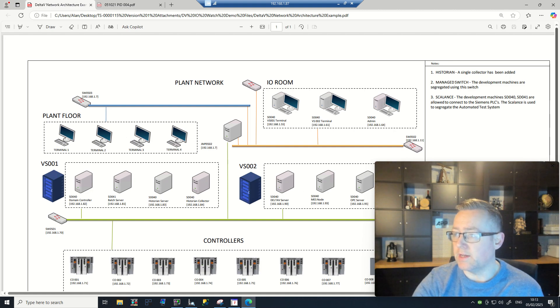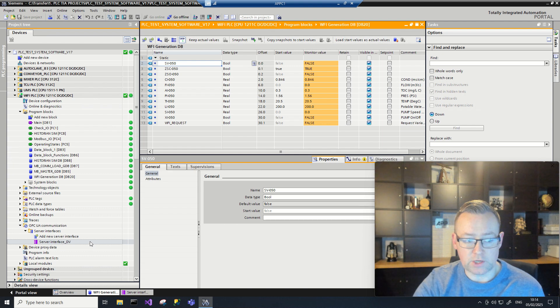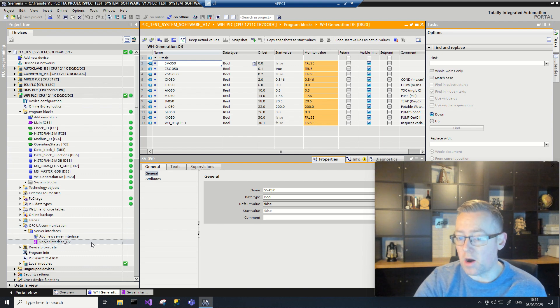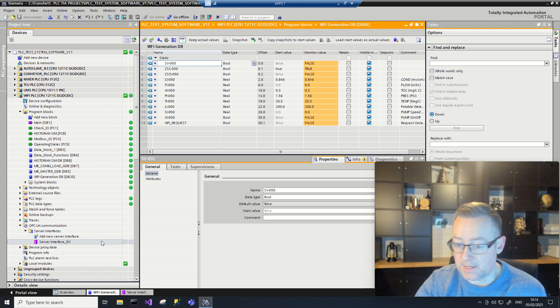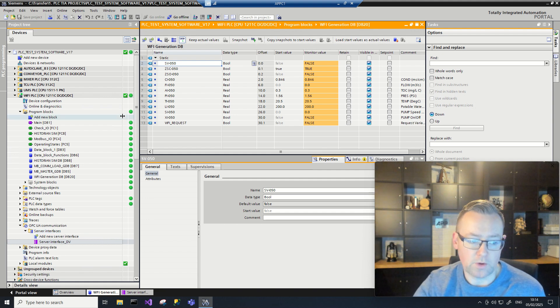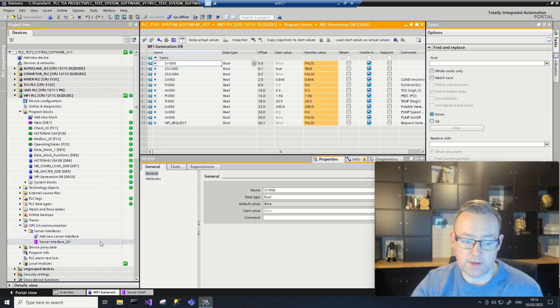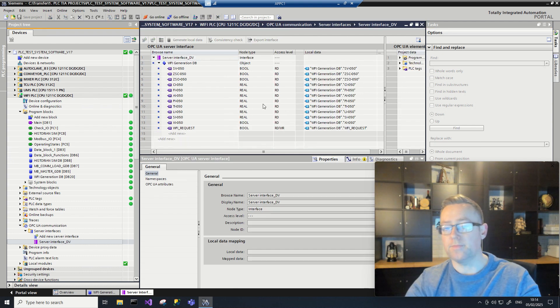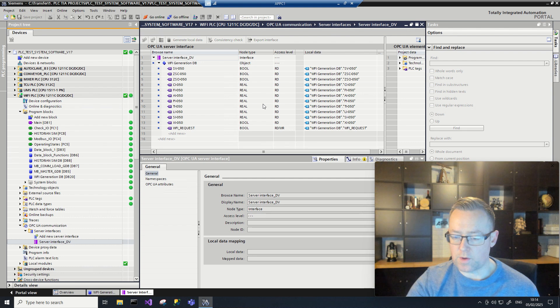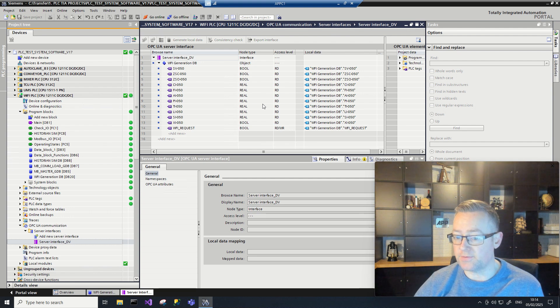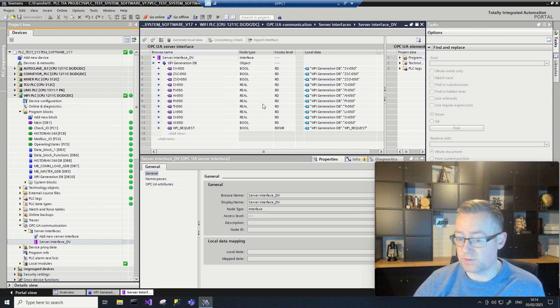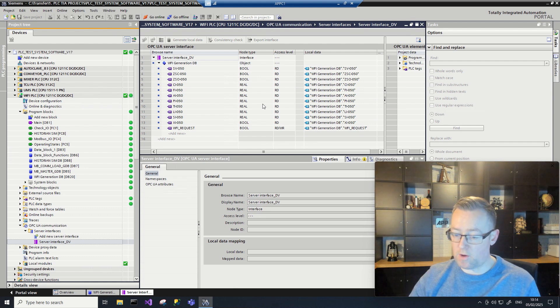But when the actual PLC has an OPC UA server set up on it, that means you can actually go direct communications. So I have a PLC here which I'm currently online to, and I have a Siemens data block set up where the data block is being exposed over OPC UA. That means Delta V, or any other system with that capability, can browse the actual tags and values without any middleware involved.